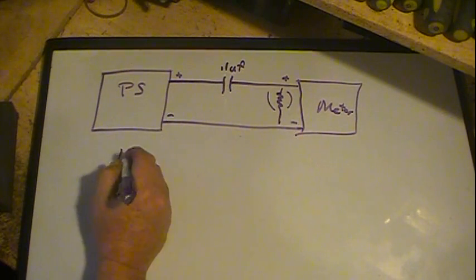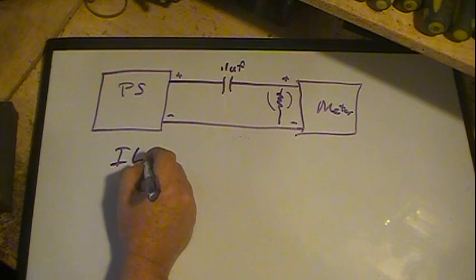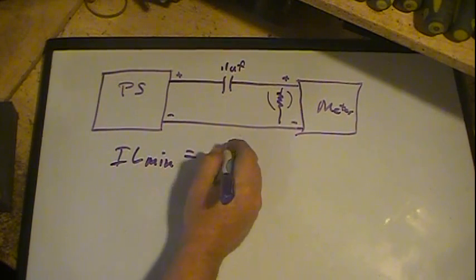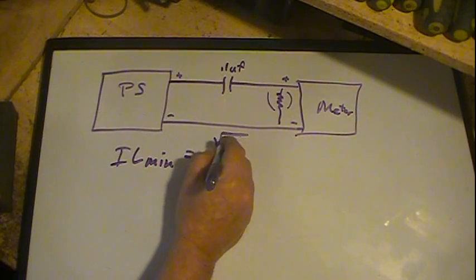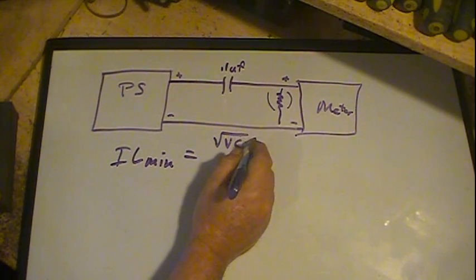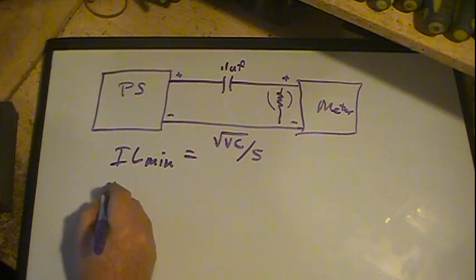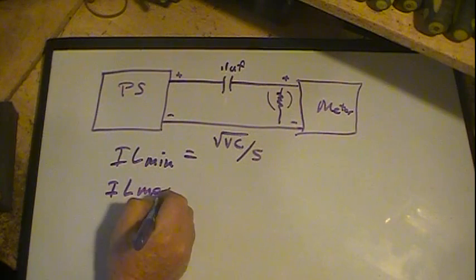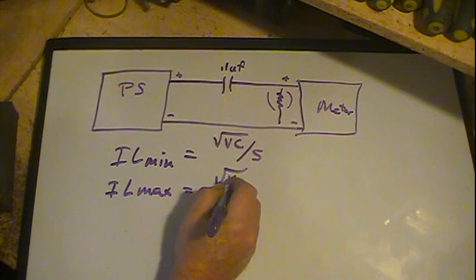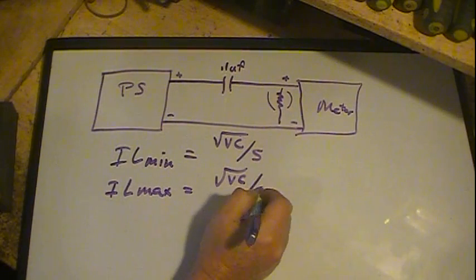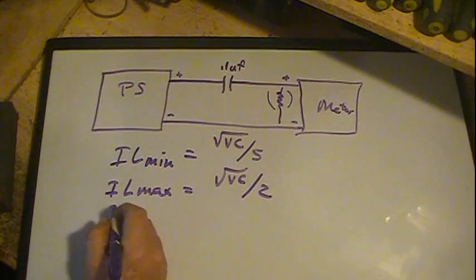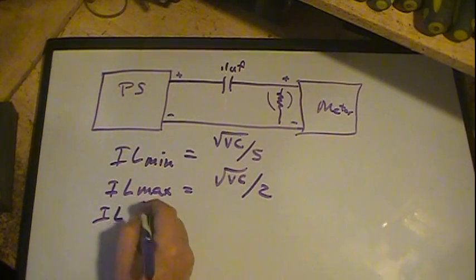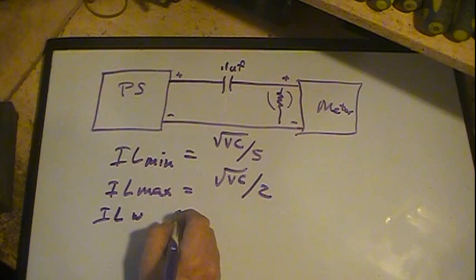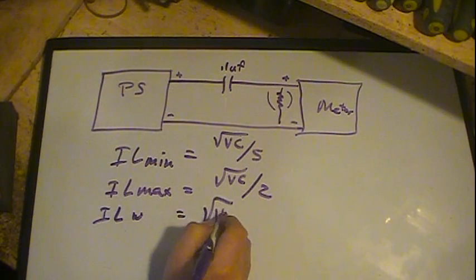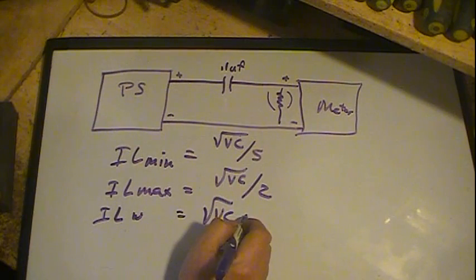Now there are a couple of formulas. Our minimum leakage is the square root of V times C, divided by 5. I'll give you what these mean here in a minute. Max leakage is the square root of VC divided by 2. And the worst case scenario leakage current, I'll just put W, equals the square root of V times C, times 6.